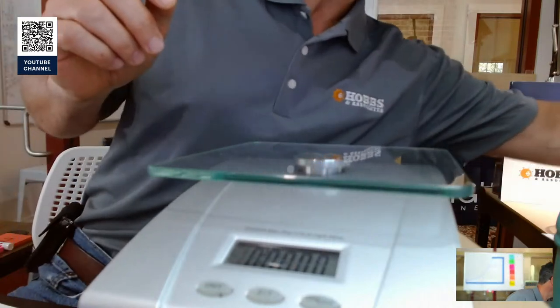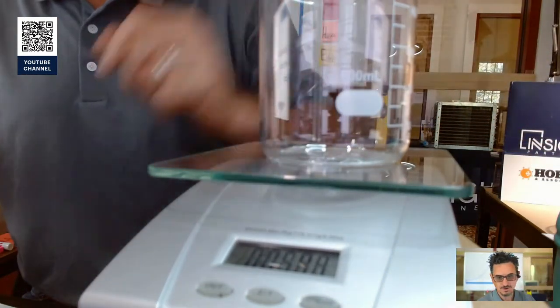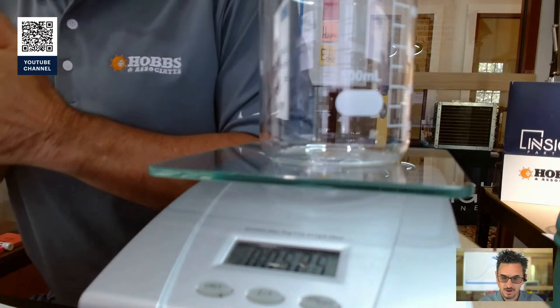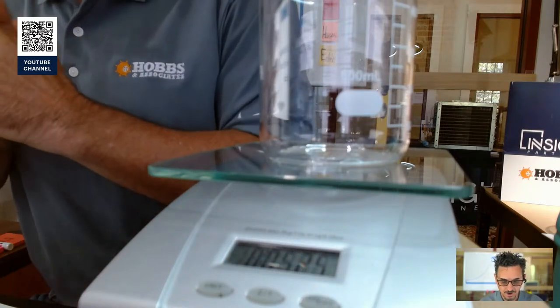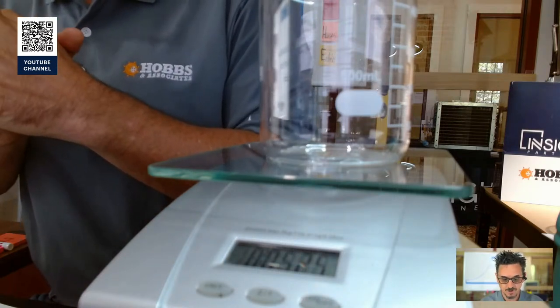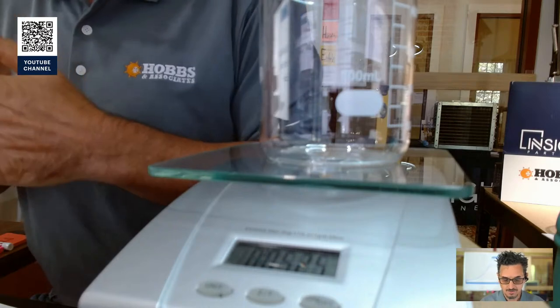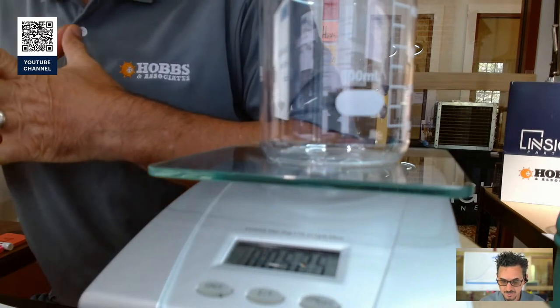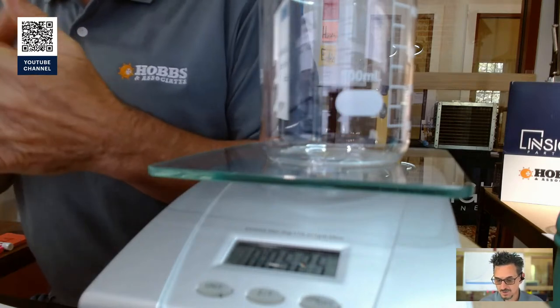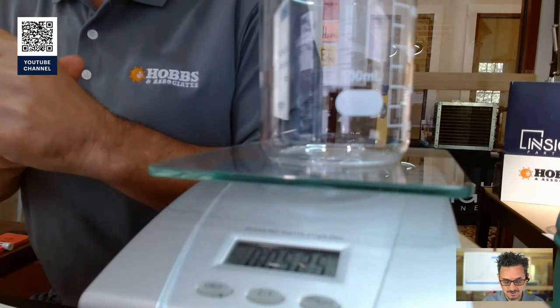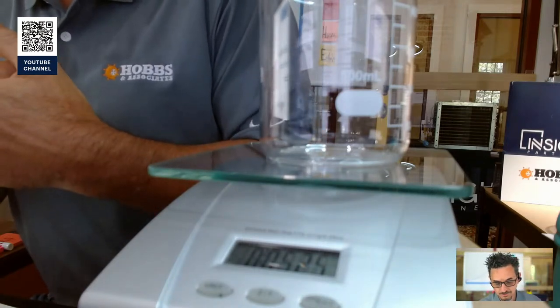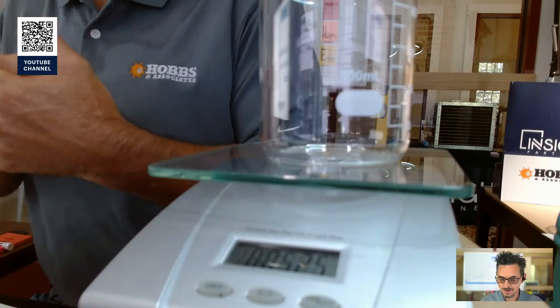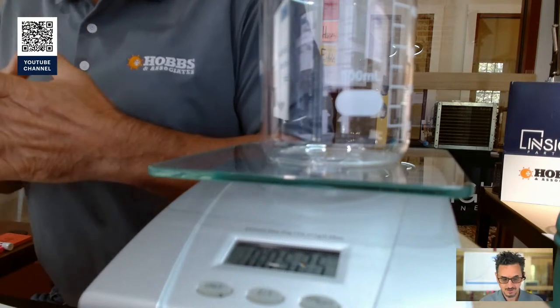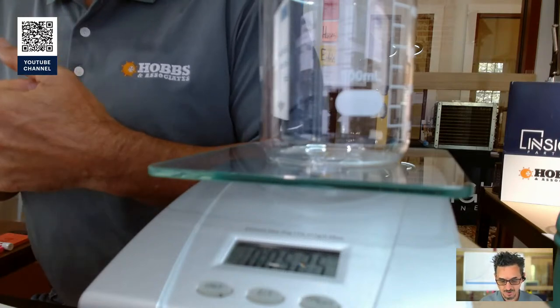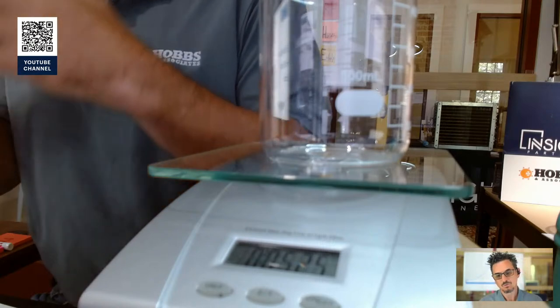Now I'm going to represent that here in a minute by using another visual aid. So on our psychrometric chart, humidity is expressed as grains per pound of dry air. A grain is a unit of weight initially based on the weight of a seed, but is now defined as 1/7,000th of a pound. It is used to weigh bullets, arrows, sometimes medication, and in our industry, the water in the air. So what does a grain per pound look like? What is a pound of air?